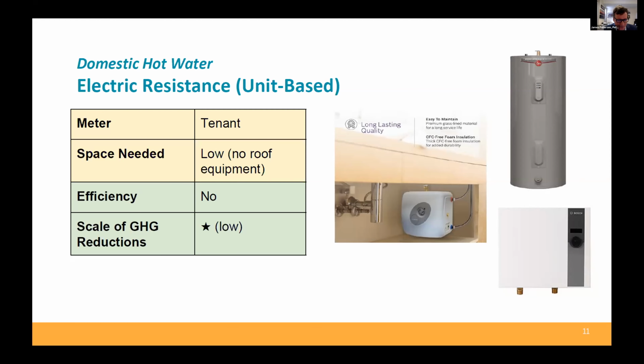Well, it's hard for me to think of the right application, because if you've been around long enough, there was a lot of electric resistance installed starting in the 60s and 70s, and then in the 80s it was being taken out of schools and replaced with fossil fuels. So electric resistance has been a dirty word for a very long time. It's basically because air source heat pumps provide a coefficient of performance, where you have one unit of energy in and can potentially get three units of energy out, using outdoor air as a heat source. Electric resistance is one unit in, one unit out.